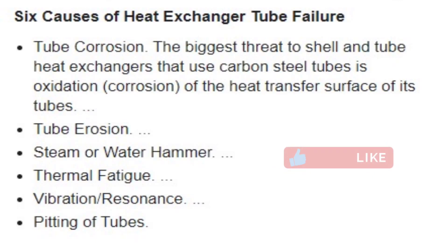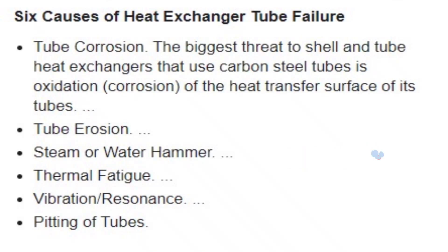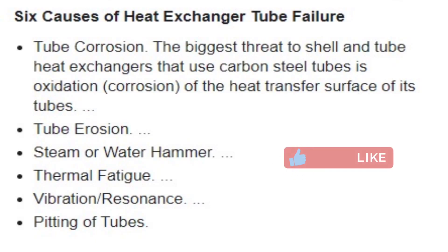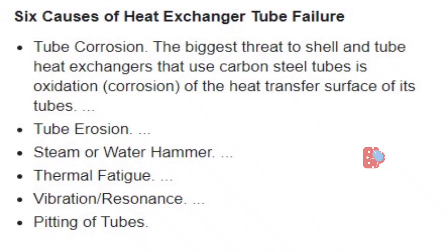Steam or water hammer is a powerful force and can cause the rupture or collapse of either the shell or the tubes of a heat exchanger. Hammer generally occurs where there has been a surge in pressure, commonly caused by a sudden interruption in cooling water flow, the rapid vaporization of stagnant water, or pump malfunction.